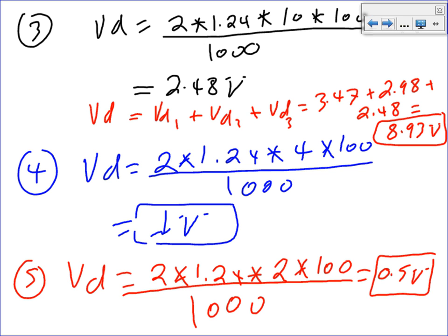Now, are we still going through the loop, right? All right, now the voltage drop percentage equals 8.97 divided by the 120 that we started with. What would you get? 7.4%. Okay, let's see where we go from here.